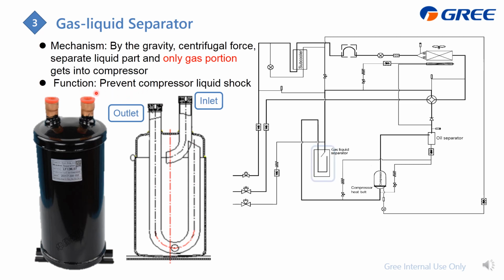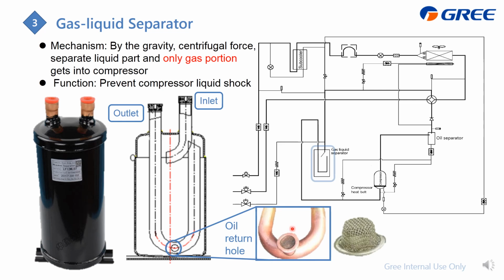And the function of it is just to prevent liquid hammer in the compressor. And you will also find a hole here, which actually is this one. There is a filter at the surface. The purpose of this one is to make the oil flow into this one to lubricate the compressor, not the liquid refrigerant.